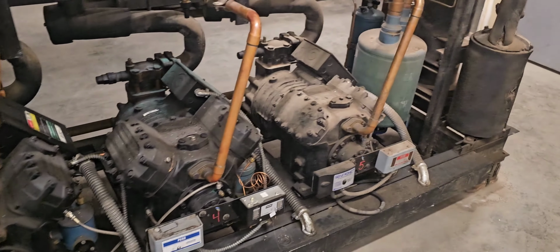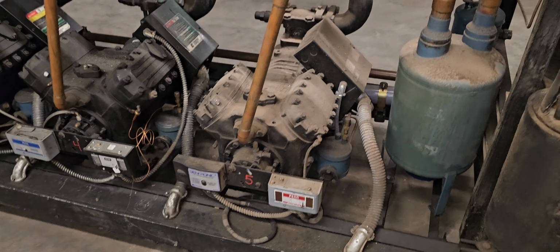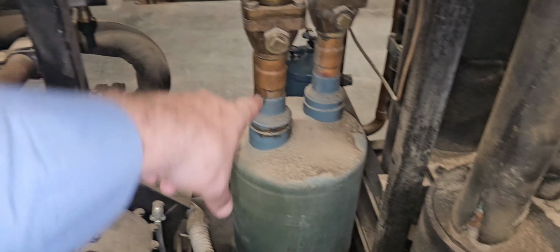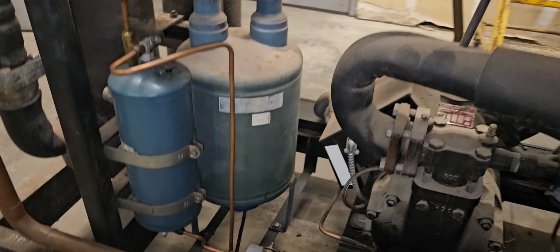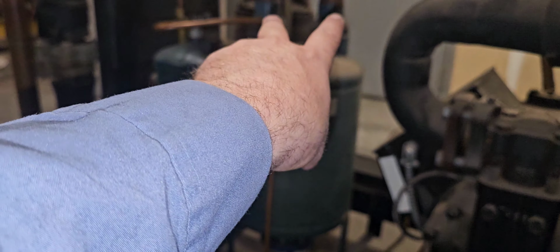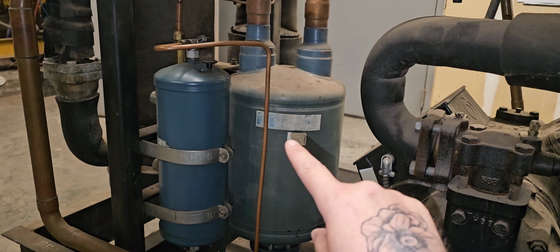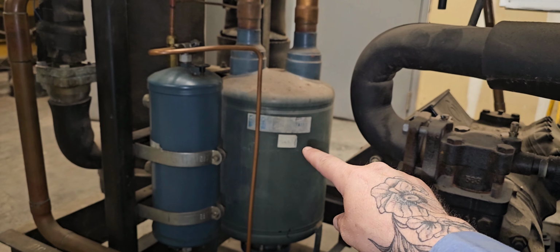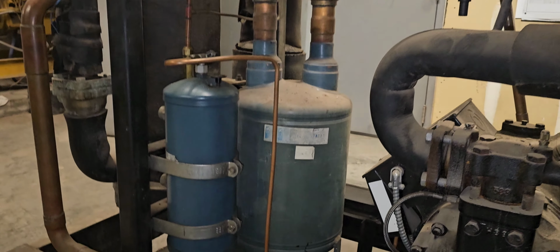So as always, your oil system is going to start and end at the compressor, right? Starting at the compressor, we've got our discharge that's going to come out and go into our separator. From that separator, you're going to separate the oil. I forget exactly what type of separator this is called, but you've got your two pipes coming in the top, which means you're going to have a sock sitting down inside this separator. That's going to separate that oil. Discharge gas is going to come in, hit that sock, separate the oil, drop it to the bottom, and then go back out on this line right here.